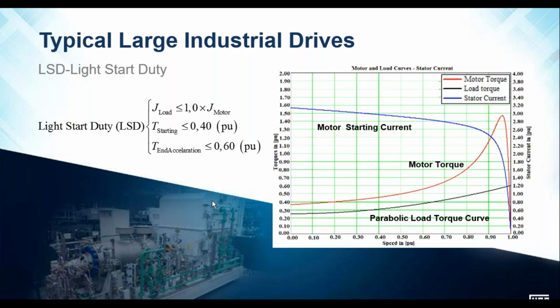applications, for example, compressors, and it is useful where your end of torque load is not your final load applied. So once this motor reaches its full acceleration, only then is the load applied. For example, on a compressor, it starts against an open valve, so there's no back pressure, and then only once the motor has reached its full speed do you close the valve and increase the load on the machine.